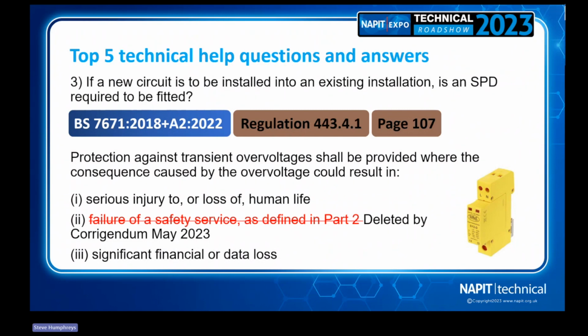And it also says they took out the actual risk assessment, so you don't have to do that complicated transient overvoltage calculation anymore. But what they do say is if the owner or the customer says they're willing to take that loss or damage, that it's tolerable to them, then that is the risk they're willing to accept in that circumstance. So there still is a risk, but it's not a risk assessment. It's more that they're taking the risk of damage to any equipment or loss they may incur.